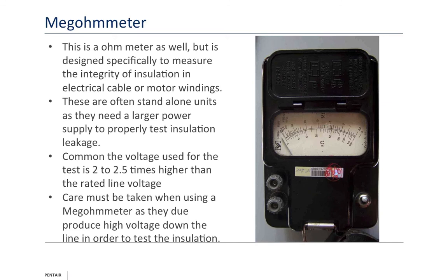So I myself often go right to 1,000, or to 500 at the minimum, to pressure test. And when you hook up your meter, in this discussion, I'll tell you, if you don't have alligator clips for your meg ohm meter, get some. You don't want to try to be holding the wire. So you connect your meter properly. You connect your probe set.